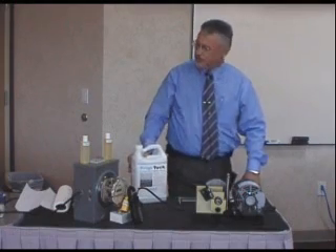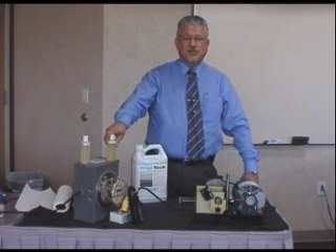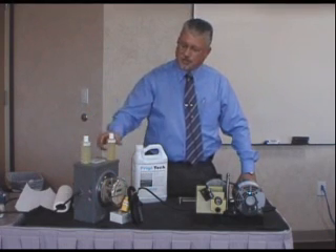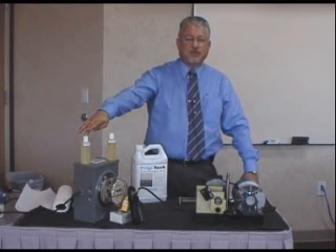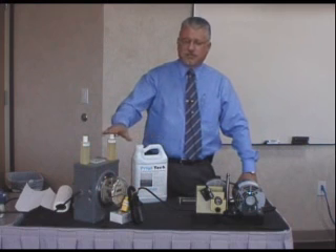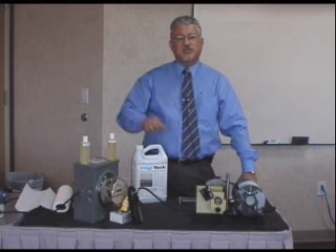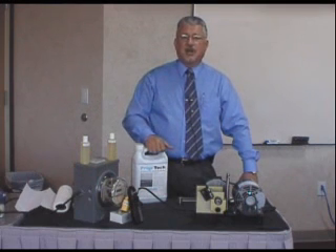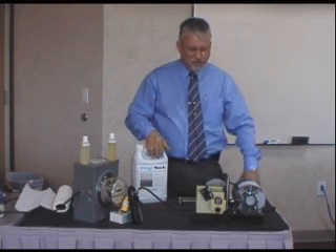What I'd like to do is demonstrate it for you. I'm going to compare Suniso 3GS, which is the industrial standard lubricant used in air conditioning systems in the United States, and then I'm going to add Frigitec to it. Color-wise they look virtually the same. Frigitec is an additive — you add it at five percent by volume on regular AC systems, and about eight percent on ammonia systems. It does not replace the standard oil; you add it to it. It can be mixed and blended with any type of oil, whether mineral or synthetic, whether you're using ammonia or Freon.